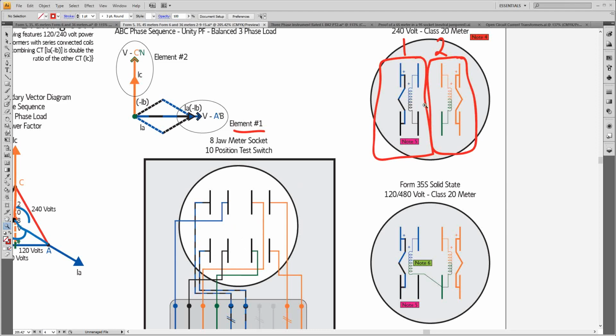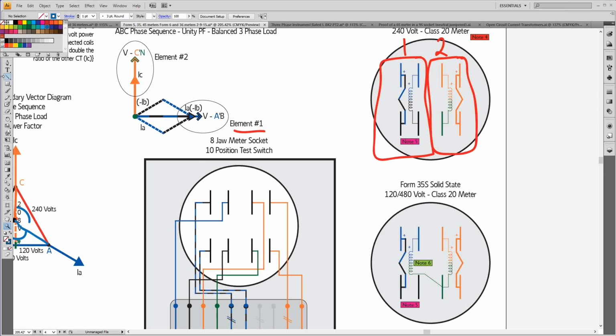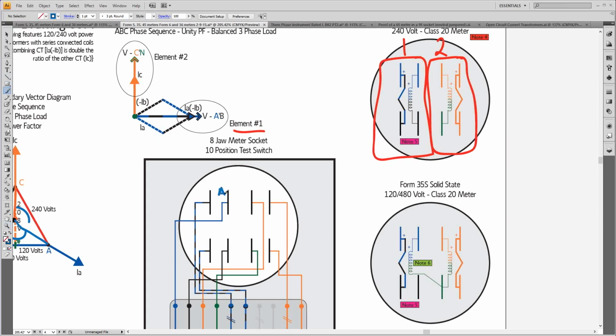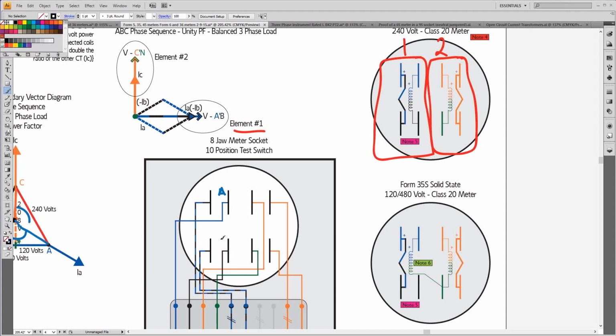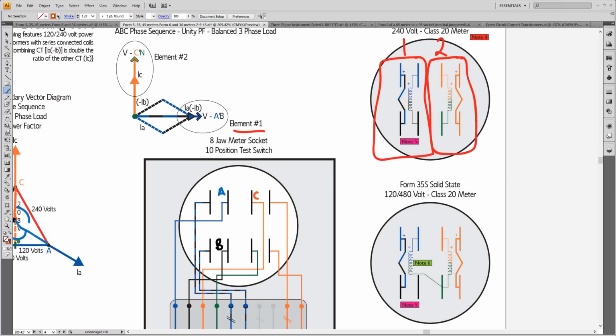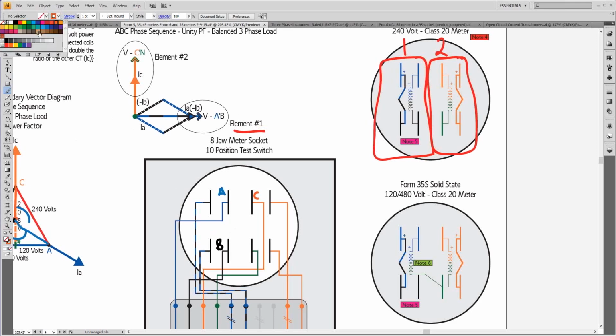As I would take this meter out and replace it with a 35S, as I plug the 35S in, I see the 35S shows the potential coil from where is A phase. Maybe I'll label those real fast. How it was wired for, oh, I need a pen. But this set is A, and this one was B, and this was C. And this is the potentials. The currents don't change from 35, 45, or 5. The currents are all the same. It's the potentials that end up changing.